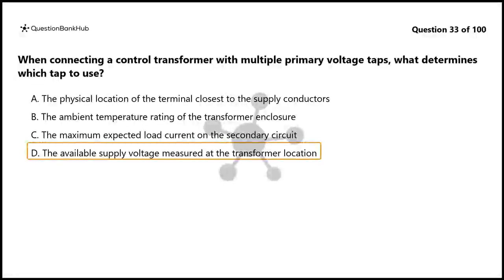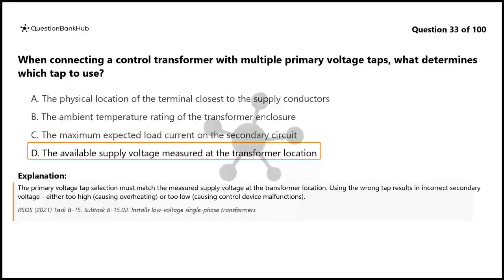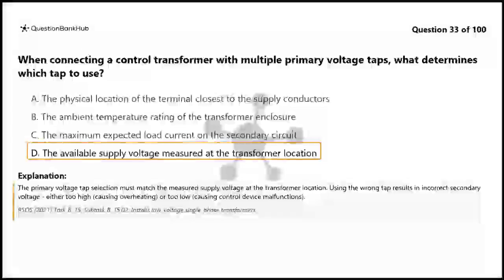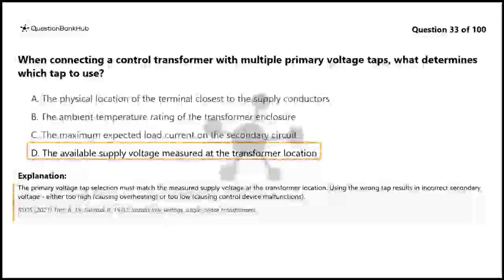The correct answer is D. The available supply voltage measured at the transformer location. The primary voltage tap selection must match the measured supply voltage at the transformer location. Using the wrong tap results in incorrect secondary voltage, either too high, causing overheating, or too low, causing control device malfunctions.